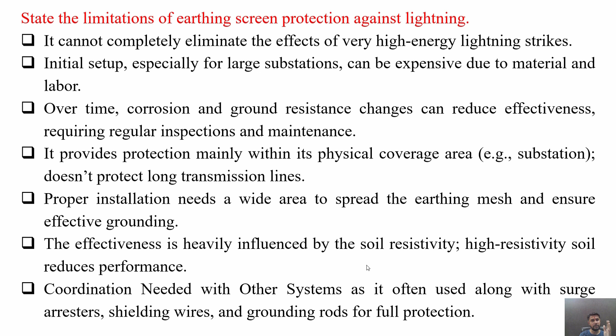Proper installation needs a wide area to spread the earthing mesh and ensure effective grounding. The effectiveness is heavily influenced by the soil resistivity. High resistivity soil reduces its performance. Coordination is needed with other systems, as it is often used along with surge arresters, shielding wires and grounding rods for full protection against lightning. So these are several limitations of earthing screen protection against lightning.